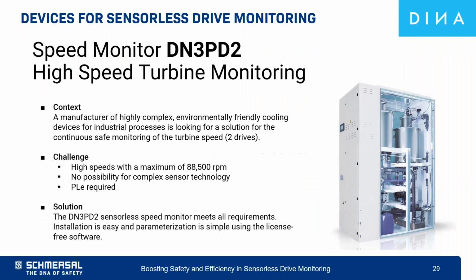And on the next slide, I brought you a nice success story or application example we did with one customer related to high-speed turbine monitoring. What you see here is an environmentally friendly cooling device for industrial processes, and it contains turbines, and these turbines run at a high speed. The maximum speed is 88,500 RPM, and the requirement here was to monitor the speed of the 2 turbine drives without using complex sensor technology, because there were also space limitations, and additionally we had the PLe requirement. And yeah, the DN3PD2 sensorless speed monitor was the perfect fit in this case, and it meets all the requirements.